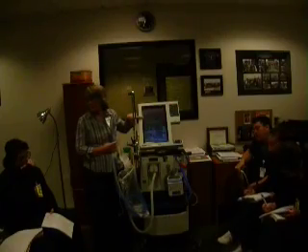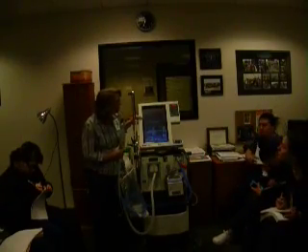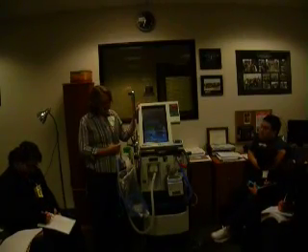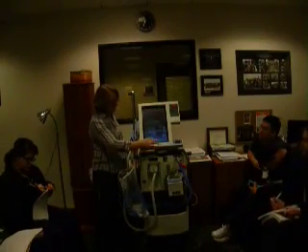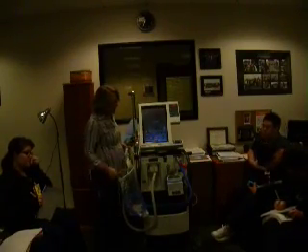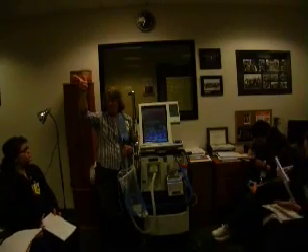So that's all that. Here's your waveforms. Graphics. Plot setup is where you can go in and change what you can see on there. And then down at the bottom we have alarms. This is our third. No, 4th. Graphics was our 3rd. 4th is alarms. So there's where our alarm settings can be set. Set parameters, patient parameters, graphics, and alarms.